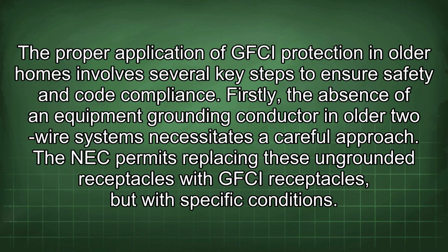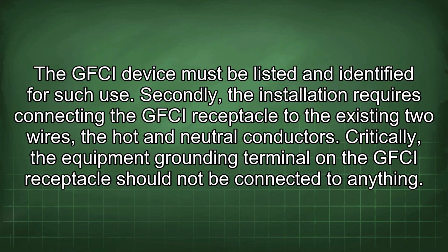The proper application of GFCI protection in older homes involves several key steps to ensure safety and code compliance. Firstly, the absence of an equipment grounding conductor in older two-wire systems necessitates a careful approach. The NEC permits replacing these ungrounded receptacles with GFCI receptacles, but with specific conditions. The GFCI device must be listed and identified for such use.